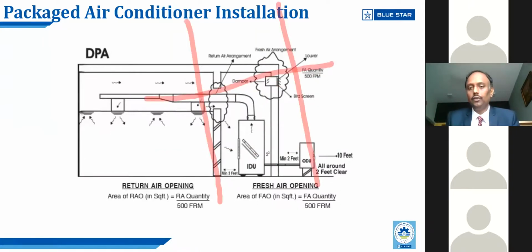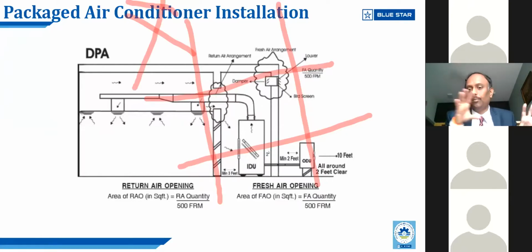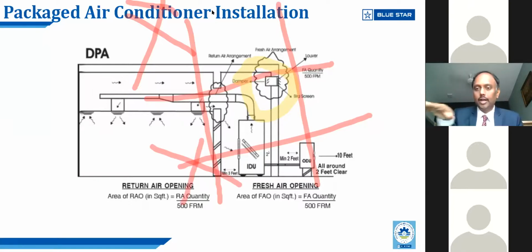The fourth important point is the height, the height of the entire thing. Now, ducting is a very important part for air conditioning engineers, and also for architects and interior designers. For you, you'll always try to keep the size or height of the ducting very small. For us, we need to design the ducting in the right size to maintain air distribution. Now, all of you need to keep one thing in mind, which is called the aspect ratio of the ducting. That means the width and height of the ducting at max can be 1:4. It cannot be beyond that.